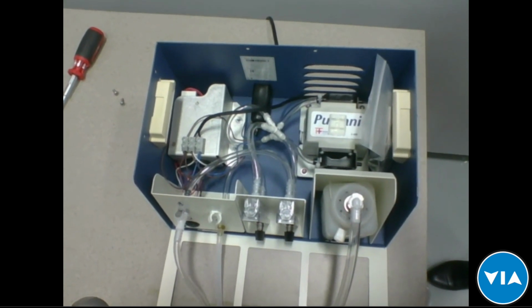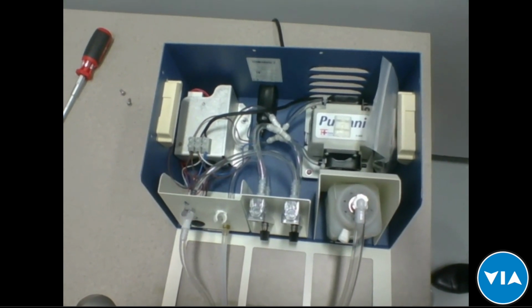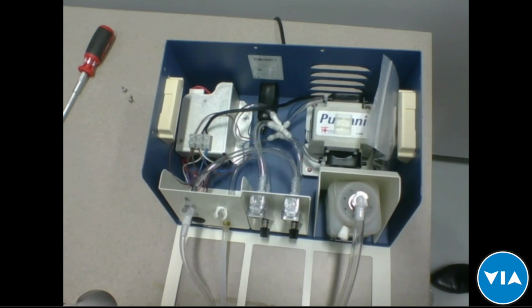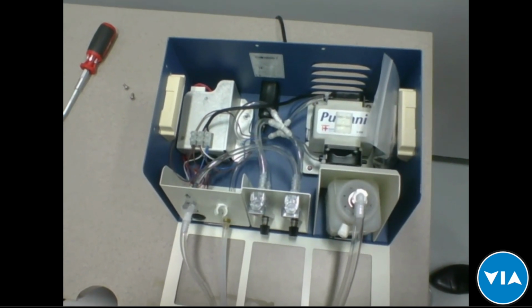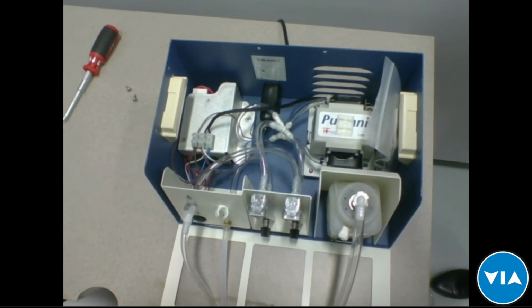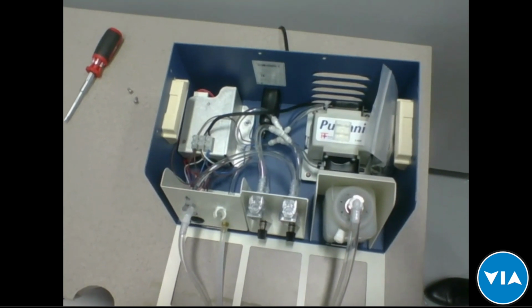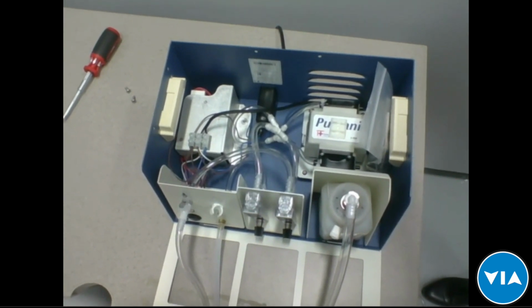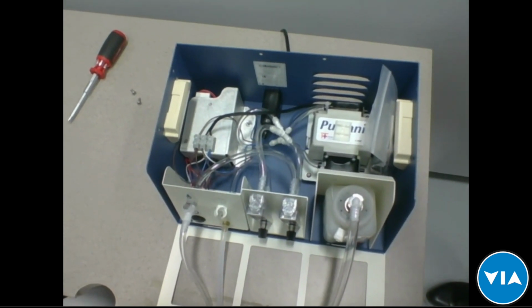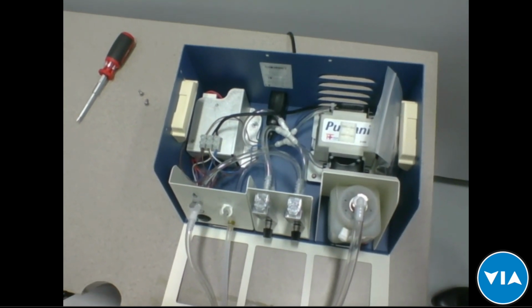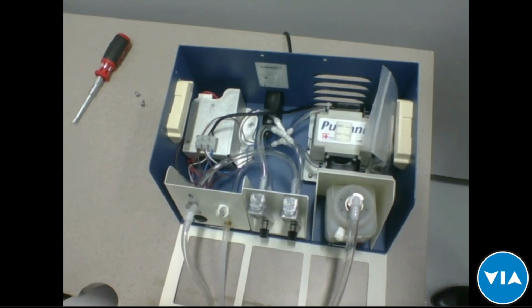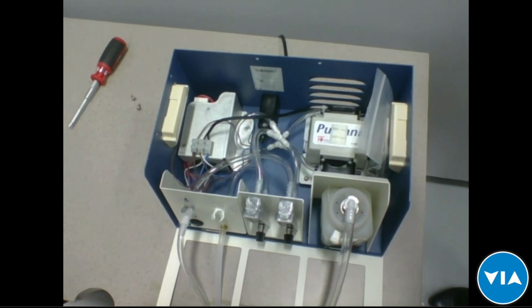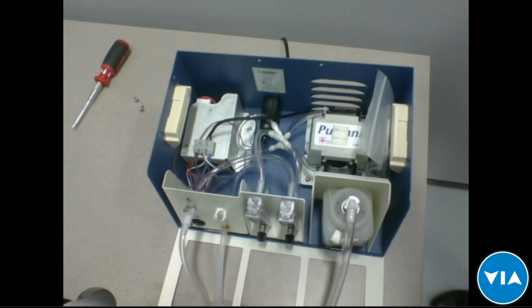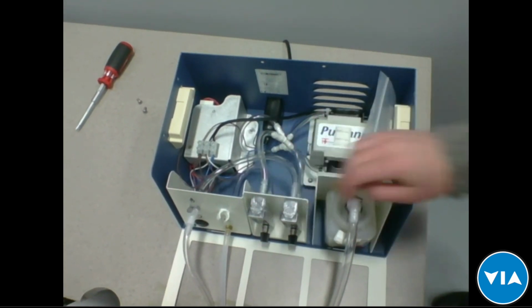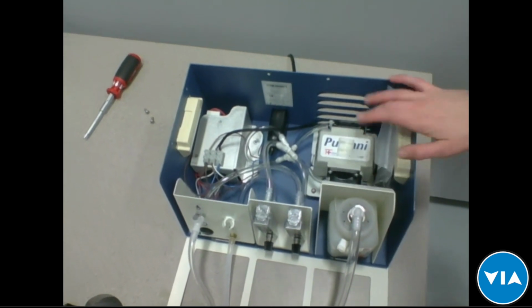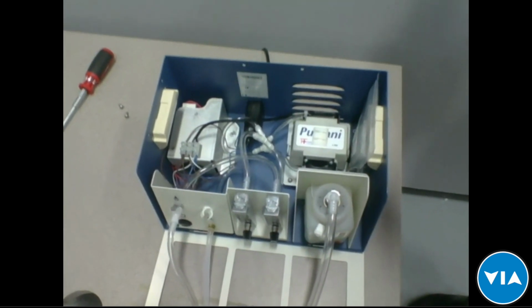Because the main things that would go wrong is that due to humidity or dust or just lack of use, something would get stuck, the beads or something would get stuck inside of the pathway, the air, the tubing. And so basically, number one thing of maintenance is turn it on once a week, check that the flow meters are working and the pump is working. That's sort of the first key thing. And that should keep it going for at least 5 years.